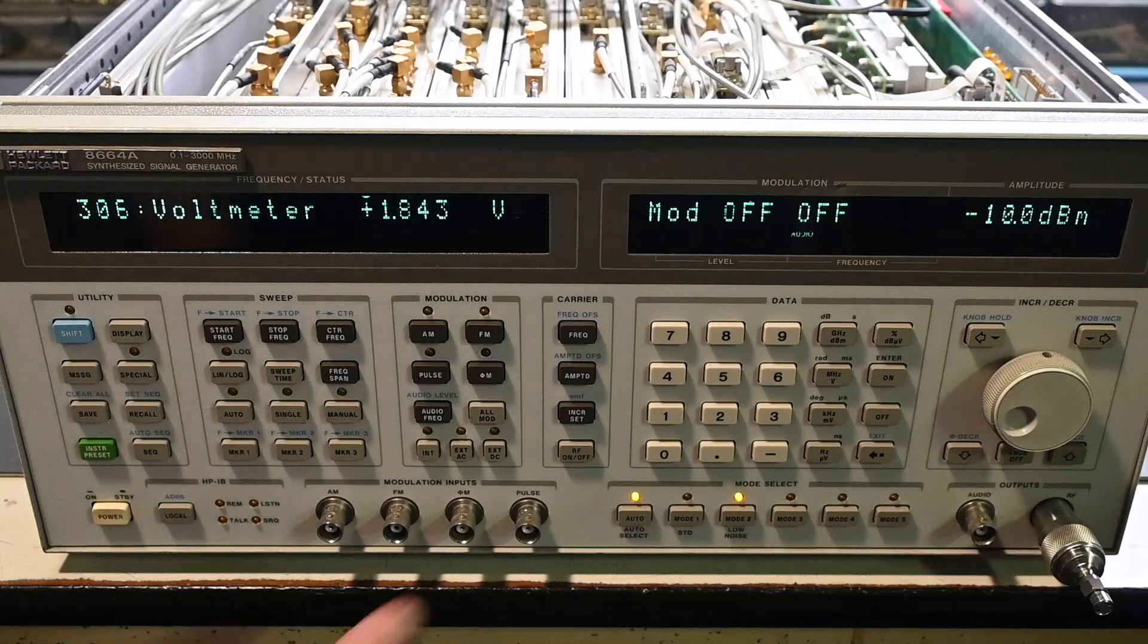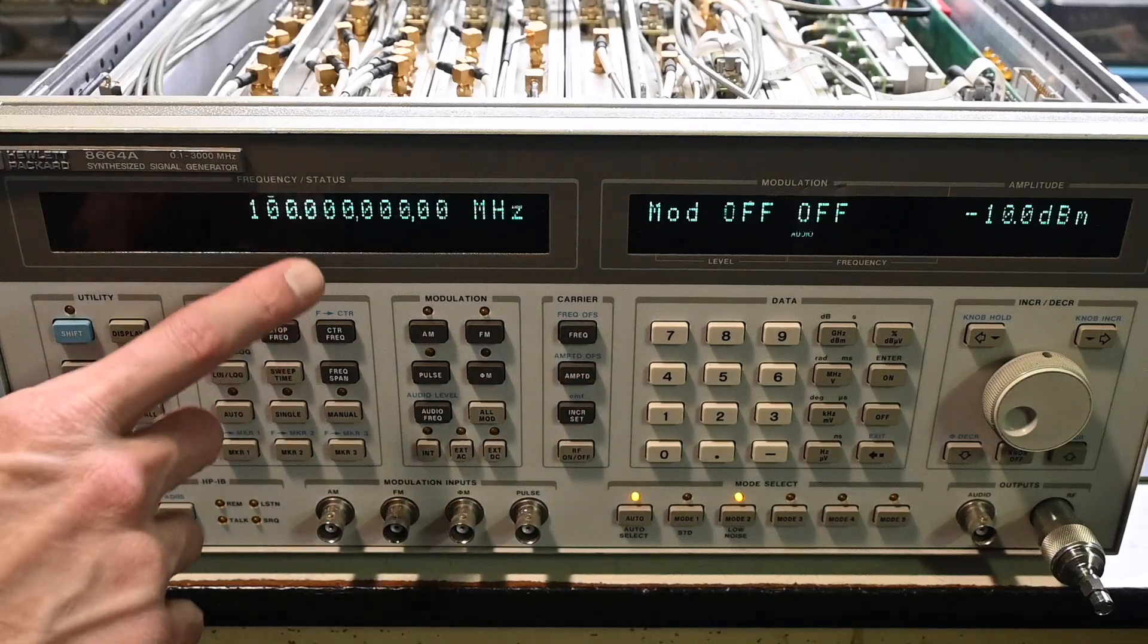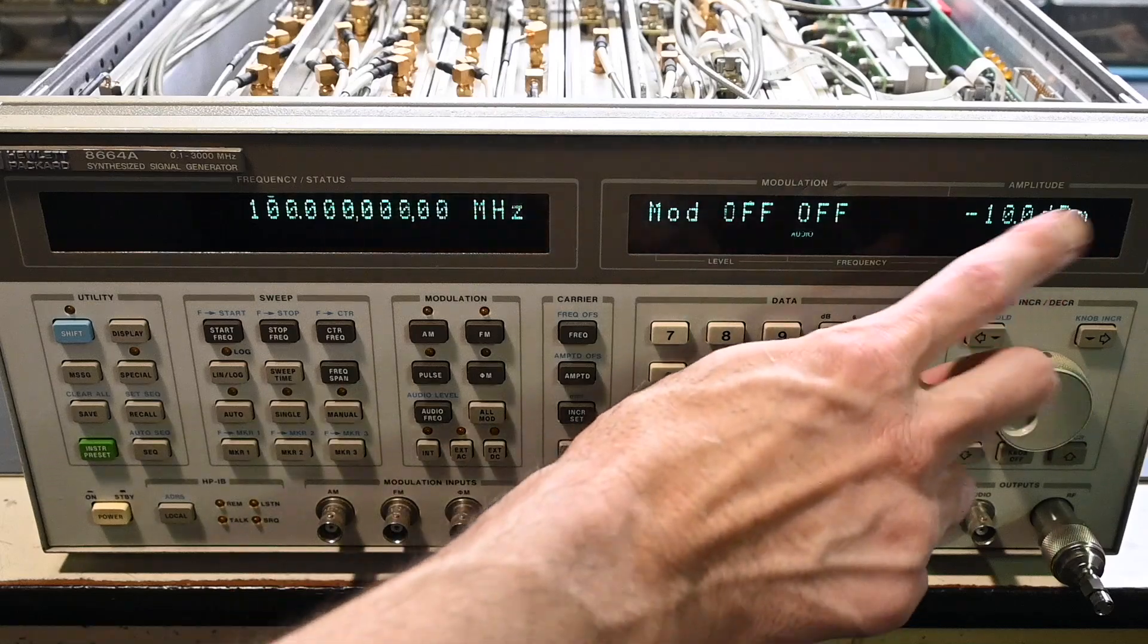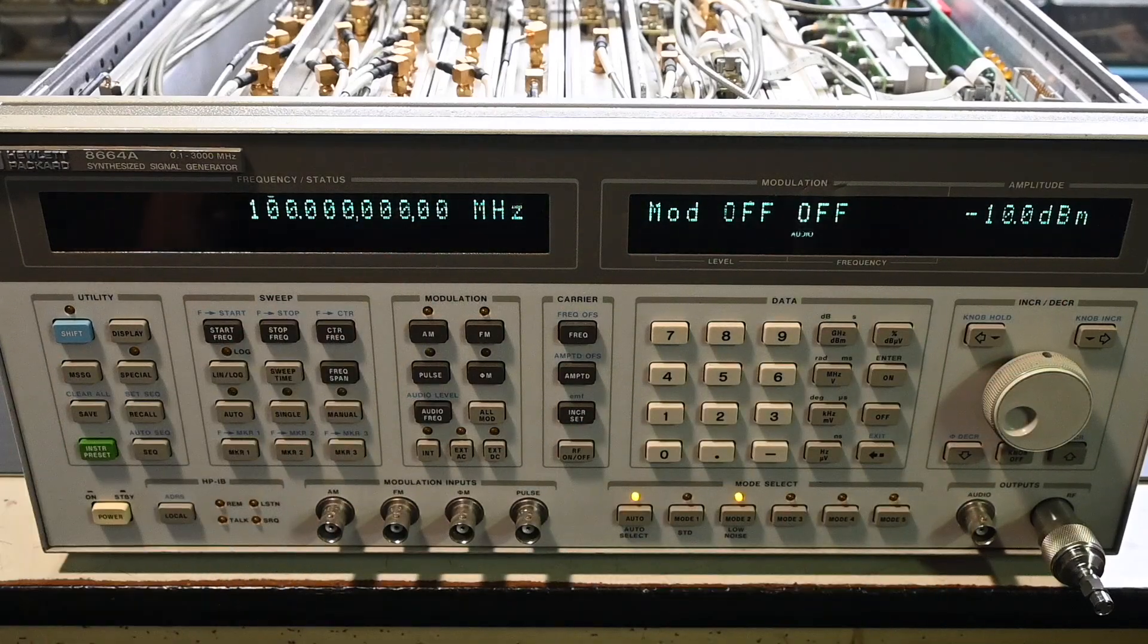So just set this back to frequency again, and the frequency has to be at 100 megahertz and minus 10 dBm for the output signal level when you take that voltage reading.